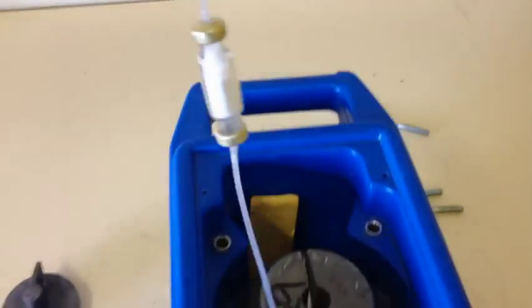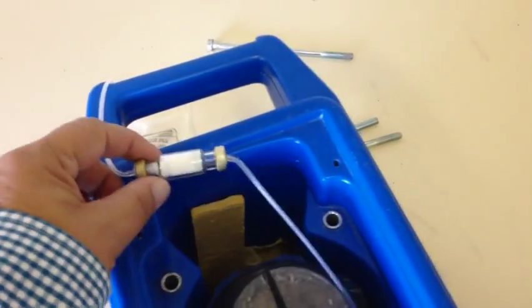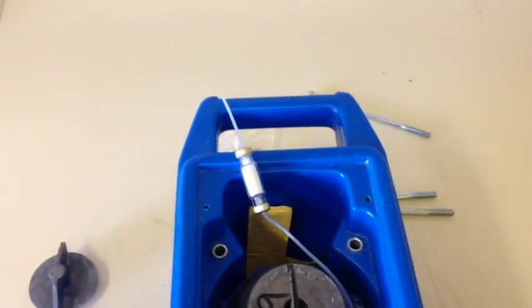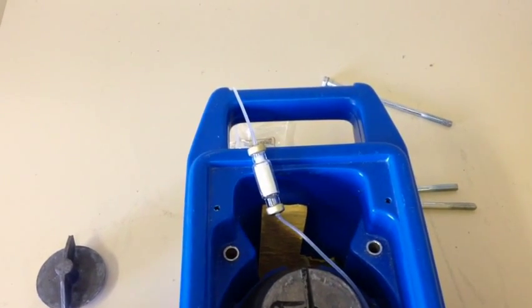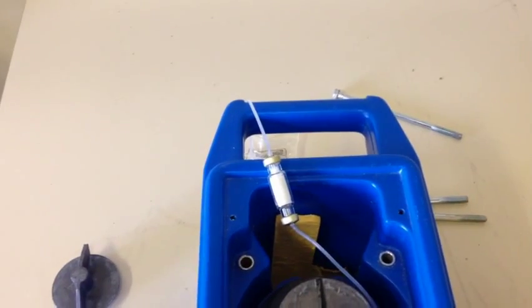But in doing that, the entire system is bathed in saline. It's just full of saline, and so this column here is soaking in saline. While generally they're pretty stable, what it can do is create some degree of instability, so you might get a little bit more molybdenum breakthrough or aluminum breakthrough.